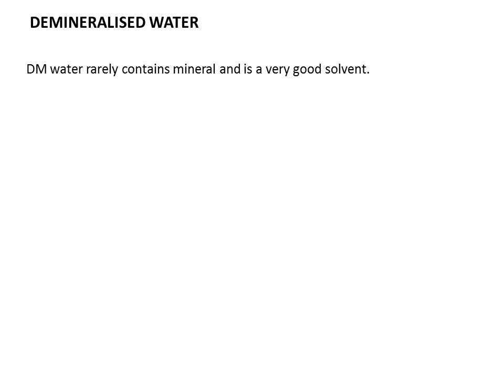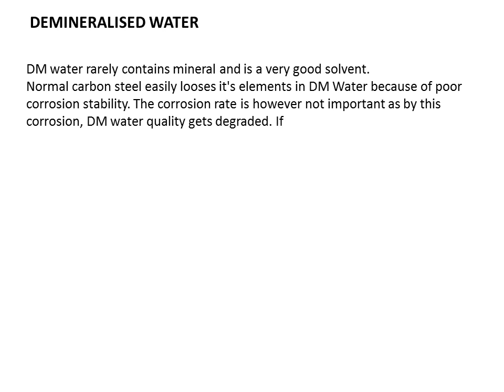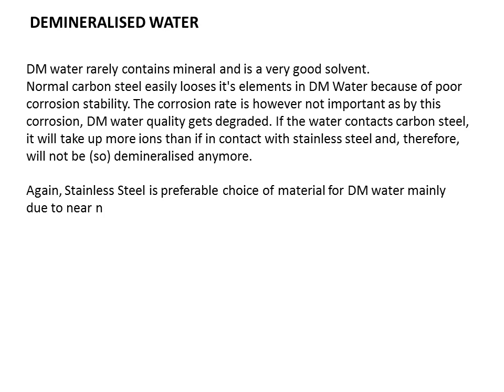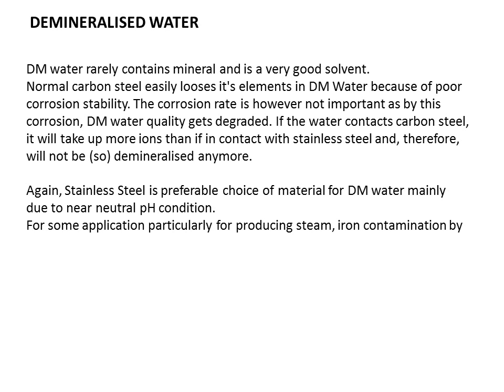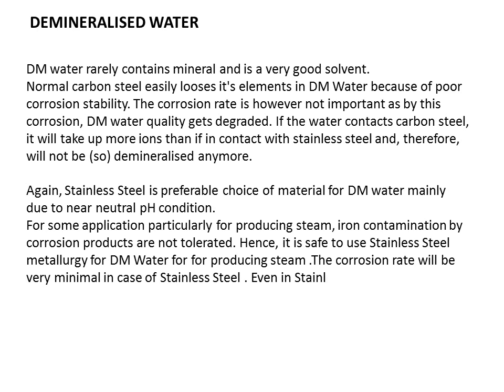Demineralized water rarely contains minerals and is a very good solvent. Normal carbon steel easily loses its elements in DM water because of poor corrosion stability. The corrosion rate is not the main concern; rather, by this corrosion, DM water quality gets degraded. If the water contacts carbon steel, it will take up more ions than if it contacts stainless steel, and will therefore no longer remain demineralized. Stainless steel is the preferable material for demineralized water, mainly due to near-neutral pH condition. For applications producing steam, iron contamination from corrosion products is not tolerated; hence stainless steel metallurgy is safe to use, with very minimal corrosion rate.